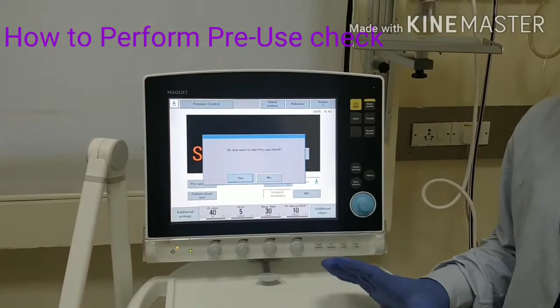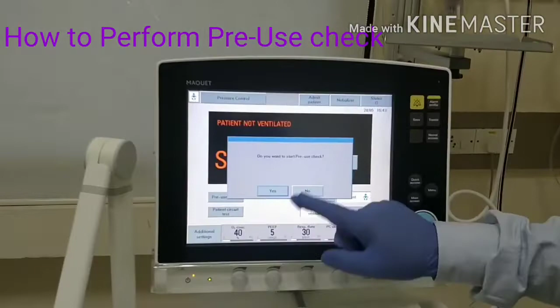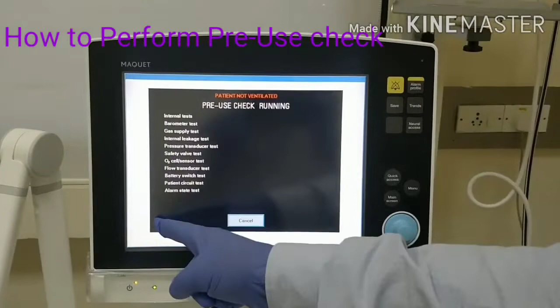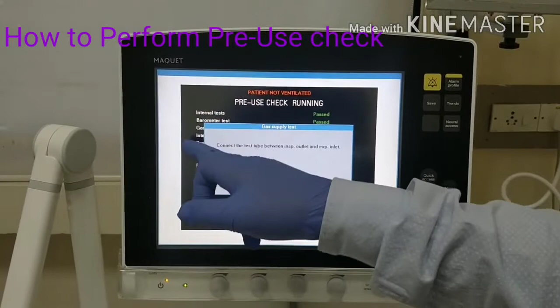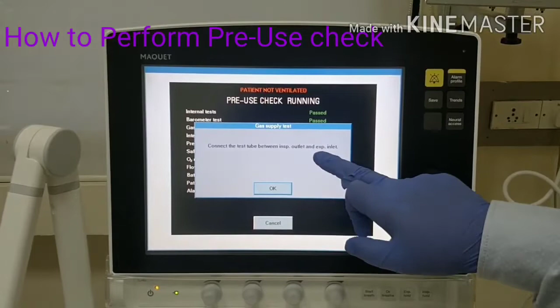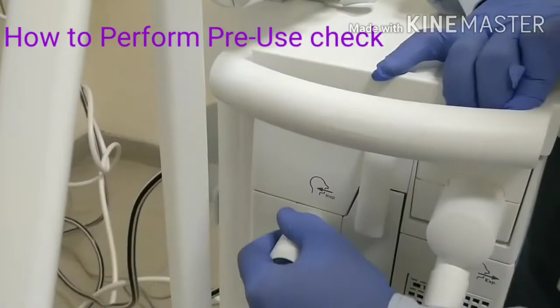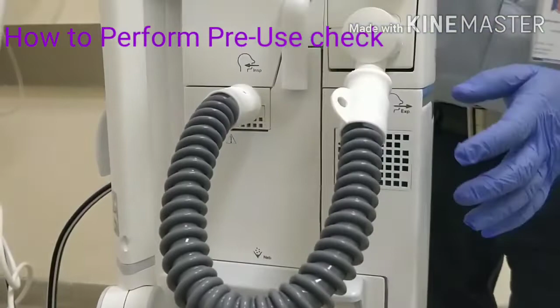Now we will see how to do a pre-use check, but before that we require one pre-use test tube. Do you want to start pre-use check? Press yes. Here are a total of 11 tests, and it will perform them one by one. After two tests it will show you one message: connect the test tube between the inspiratory outlet and expiratory inlet. So you have to connect this pre-use check tube at the inspiratory outlet and expiratory inlet. After connecting this pre-use check tube, press OK. So it will continue.